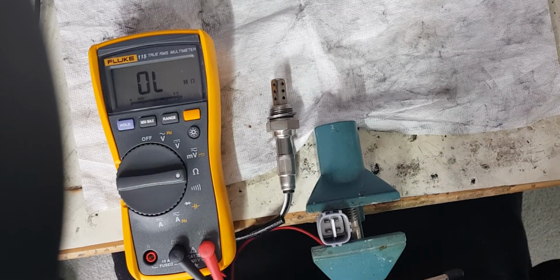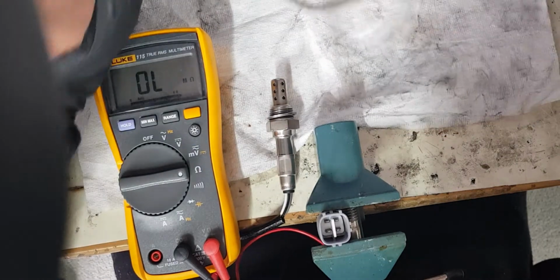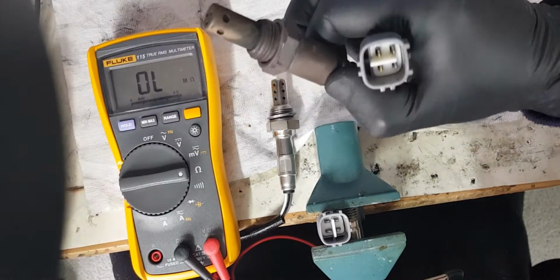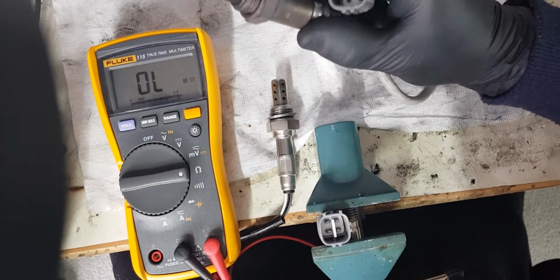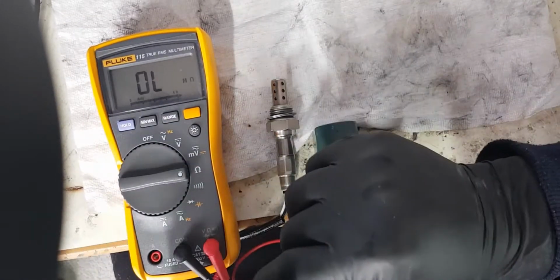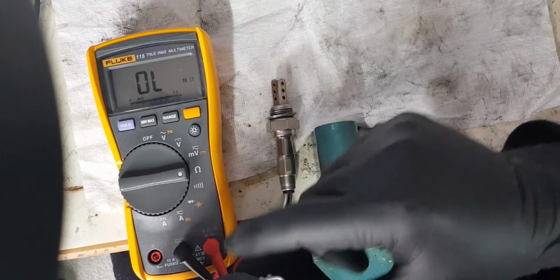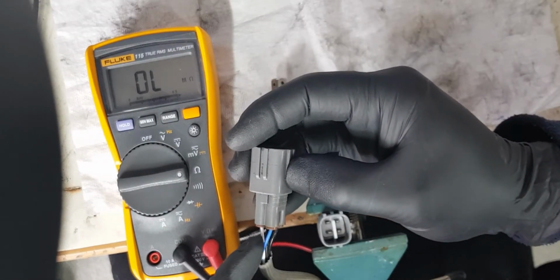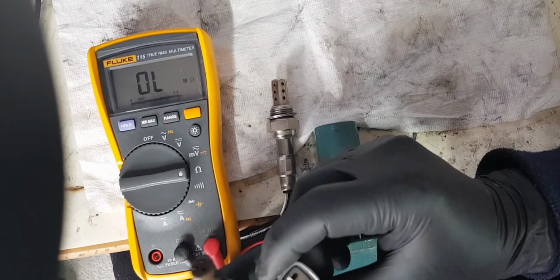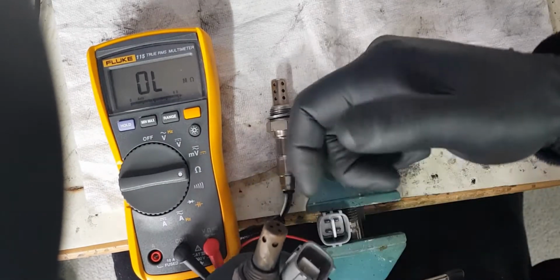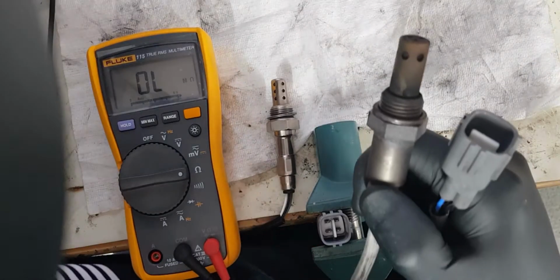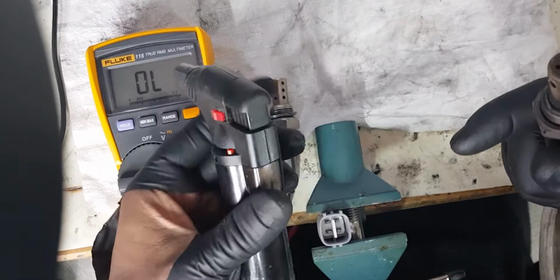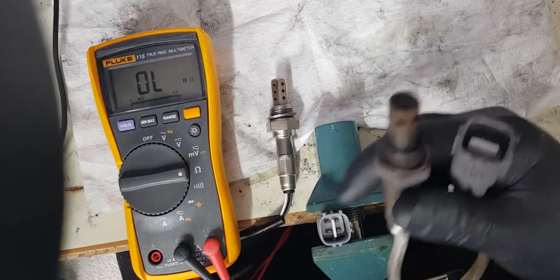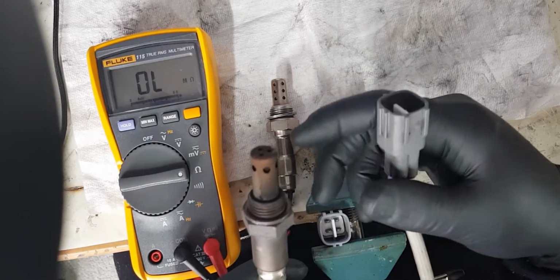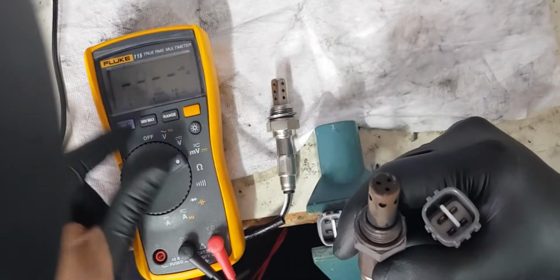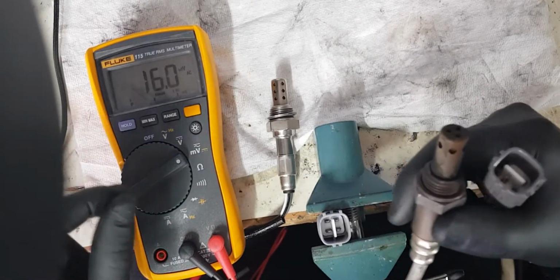If you really want to be sure the sensor works or is faulty and you can't confirm with your multimeter, what I've done previously is connect the multimeter on millivolts to the two probes, the white and the blue, and heat the front of this with a blowtorch, similar to this torch I use, but you need a bigger one, a butane torch from your local hardware store. You heat this up and watch if the reading gets closer to 1 volt, which confirms it.